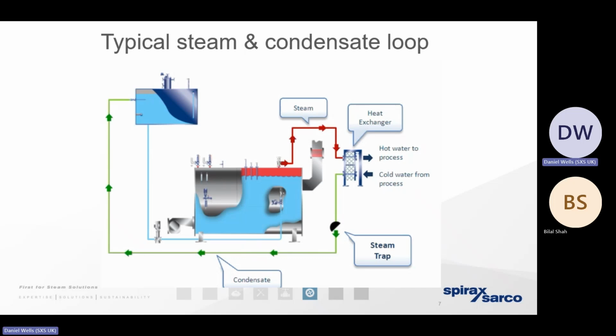The problem is, once that condensate's gone, we need to make sure that we're not losing the steam as well. That's why we've got a steam trap that's located very close to the heat exchanger itself. Think of a steam trap as being an intelligent non-return valve. It's capable of telling the difference between the steam as a gas with that high energy content and the condensate as a liquid with very, very little energy present within it. It can tell the difference between the two. So when there's condensate present, the trap will be open. And when the condensate's gone, the trap will close to prevent that inefficiency. And therefore, the boiler doesn't have to work as hard. Our cost of steam, our cost of gas, and our carbon emissions are going to be kept to the absolute minimum.